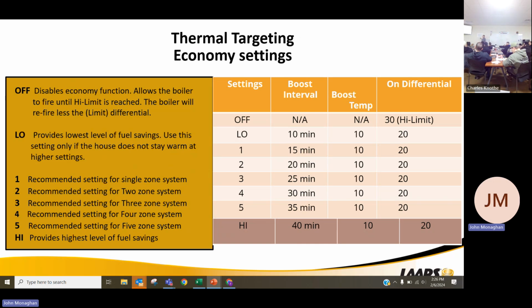We put it on low. Boost interval is going to be every 10 minutes. It's going to raise it 10 degrees if it has not satisfied. Every half hour the boiler's off, it's going to lower the set point temperature by 5 degrees. And it's going to work it back down to 180, work it back down to 160. Then it'll work its way back up. It's constantly looking to drive itself to the lowest possible water temperature to heat the home. Yes. It's going to use the least amount of energy to satisfy demand.